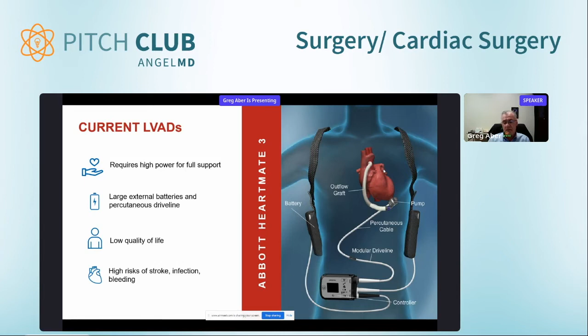This has been kind of the holy grail of this field for 30 years or so. And we feel the big stumbling block has always been the power consumption of the pump. So we focused on developing a very high efficiency pump design, about 5 to 6 times more efficient than the HeartMate 3, around 1.5 watts. So this low power consumption then allows for an implantable power source about the size of a large pacemaker.